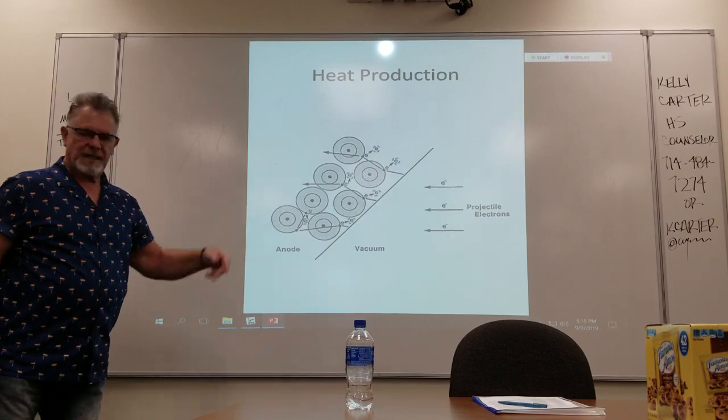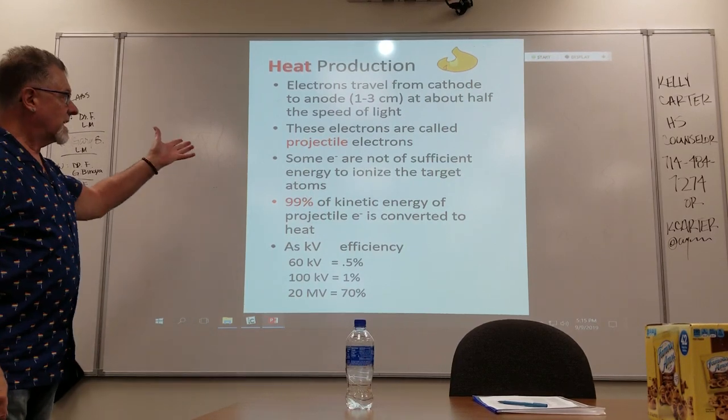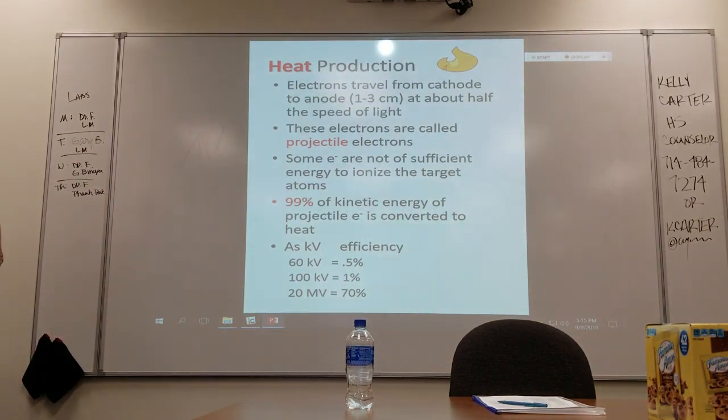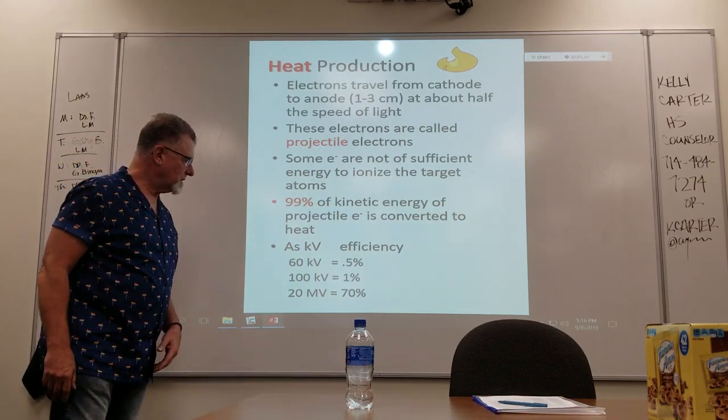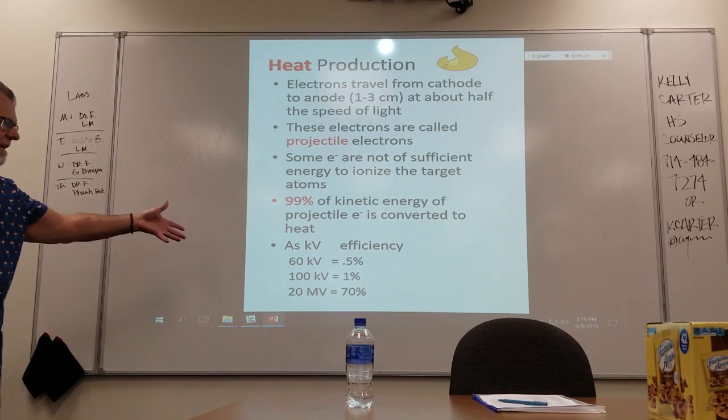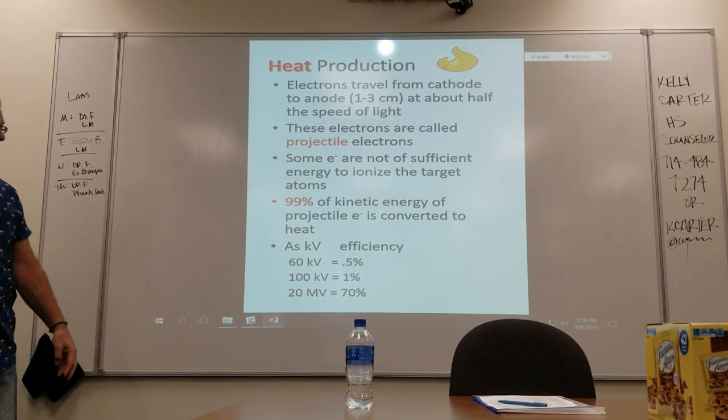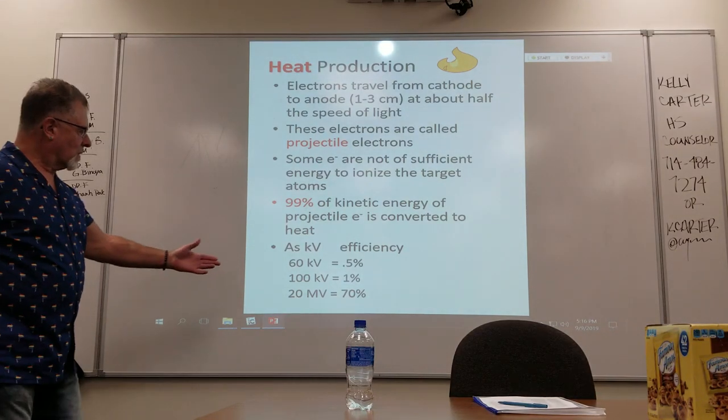You got electrons going from the cathode to the anode at about half the speed of light, called projectile electrons. Some are not of sufficient energy to ionize the target atoms, so 99% of kinetic energy of the projectile electrons is converted to heat. As far as the efficiency of producing voltage at 60 kV it's about a half a percent efficient, 100 kV is about one percent, 20 million volts like in therapy is about 70 percent efficiency. So where's the other 99% go? Heat.